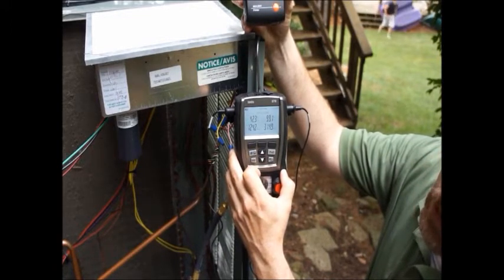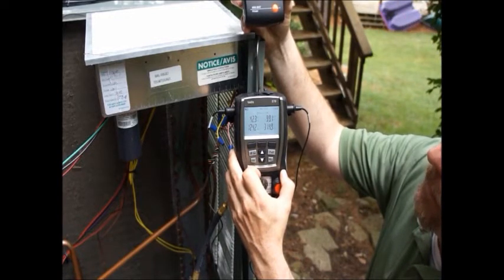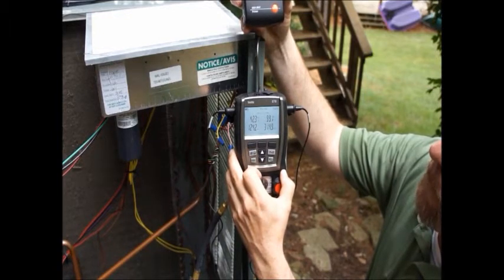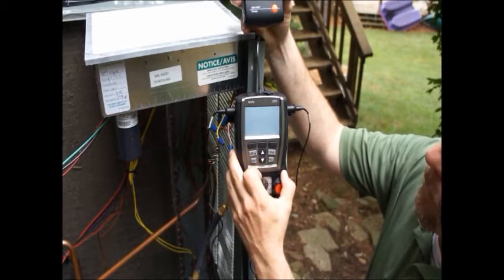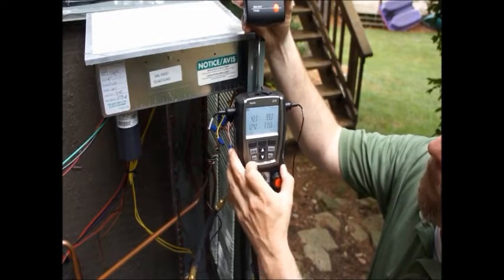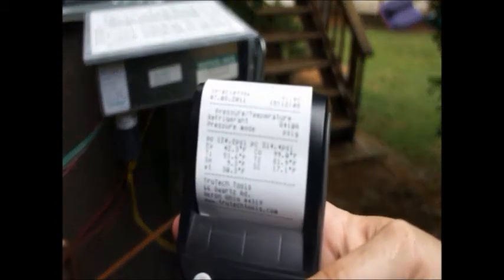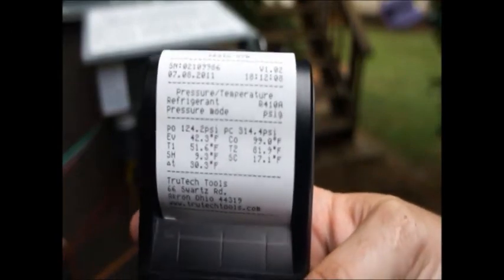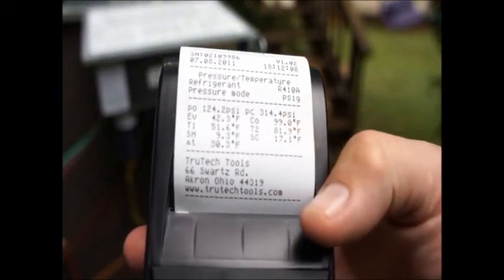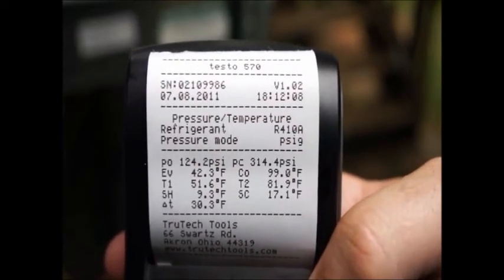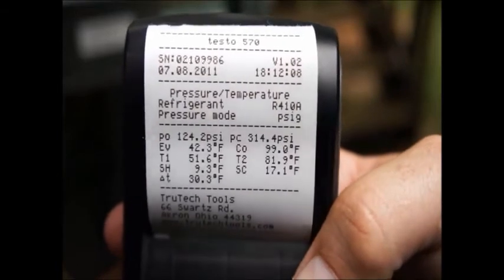We'll give this just a second. I haven't tested it with the newer printers to see if they're any faster or not. You can see there we've got our superheat, our subcooling. The cool thing is we can print out our report. The company name and address can be put onto that report if you want. You can see we've got the Testo 570, the serial number, the instruments, the pressures, corresponding temperatures and the company address.